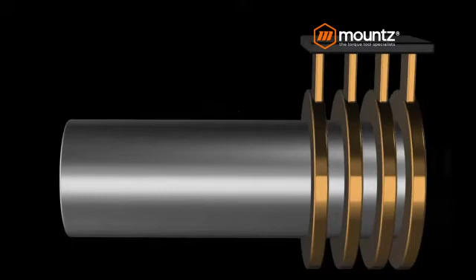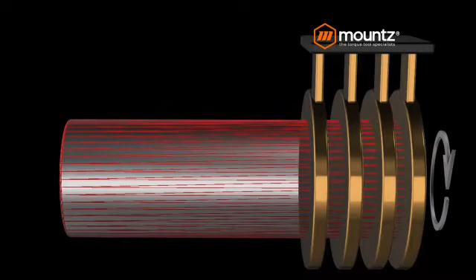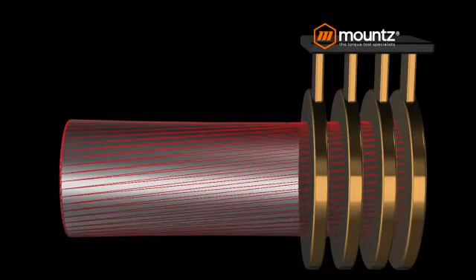Some differences with static torque measurement and static sensors: static sensors have a strain gauge mounted on the shaft, and as torsion is applied on the shaft, the resistance built in the circuit is going to measure the variation due to the torsion, and then send out the torque that was applied on the shaft. When we look at dynamic sensors, we have slip rings mounted on the shaft, and as torsion is applied on this shaft, the slip rings will move differently depending on the torsion applied. We can then read the difference between each of the slip rings, turning the analog signal into a digital torque reading.